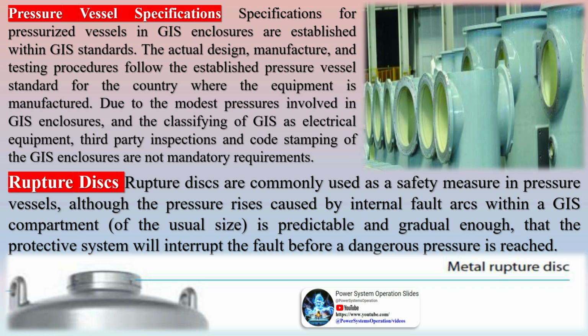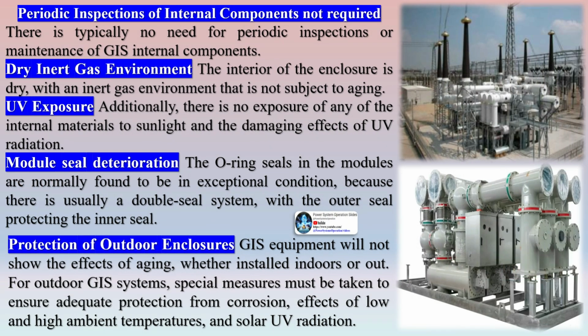Specifications for pressurized vessels in GIS enclosures are established within GIS standards. The actual design, manufacture, and testing procedures follow the established pressure vessel standard for the country where the equipment is manufactured. Due to the modest pressures involved in GIS enclosures, and the classifying of GIS as electrical equipment, third-party inspections and code stamping of the GIS enclosures are not mandatory requirements.